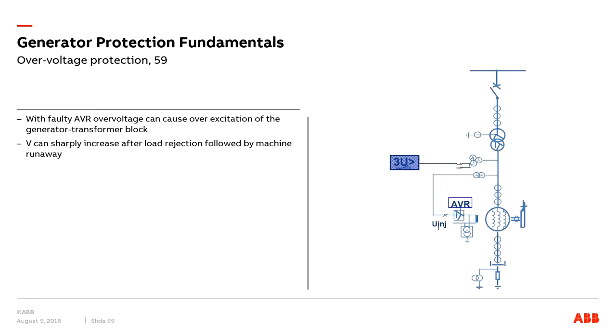Then we have the over voltage protection 59. Over voltage conditions will occur in the power system during abnormal conditions such as sudden power loss, tap changer regulating failures, open line ends, and on long lines. This function can also be used for open conductor detection or switching on and off of reactors and capacitors when combined with the directional reactive power function.